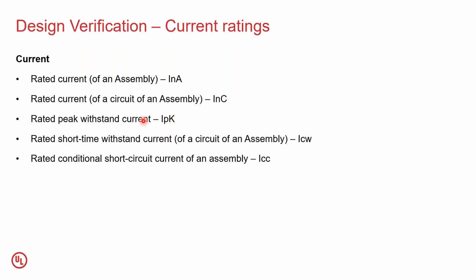While the rated peak withstand current actually comes from the standard, the rated withstand current can be declared by the manufacturer in consultation with the consultant or the end user. Now, there is another important short circuit rating called the rated conditional short circuit current of an assembly. This is always applicable when you have a protective device.